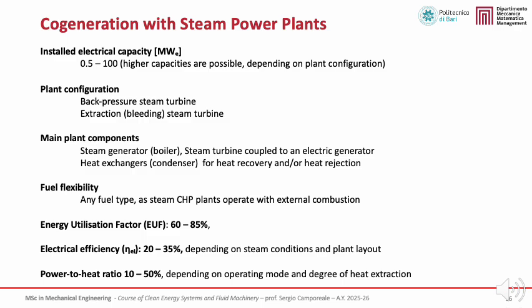They typically cover installed electrical capacities from a few megawatts up to several tens of megawatts and can be configured with back pressure or extraction steam turbines. Thanks to external combustion, these plants offer high fuel flexibility. Their overall efficiency, expressed through the energy utilization factor, can reach values between 60 and 85%, while electrical efficiency typically ranges from 20 to 35%.